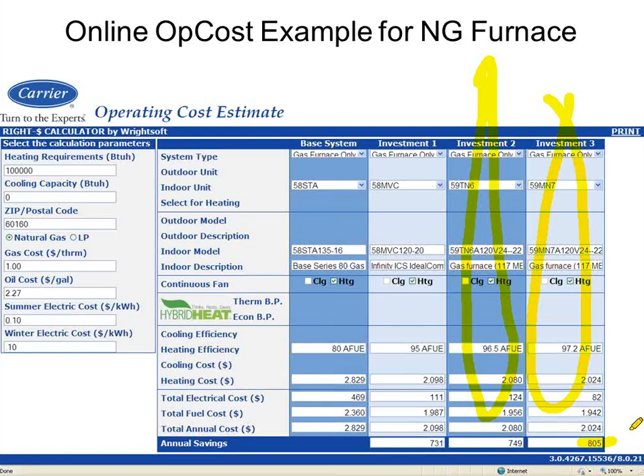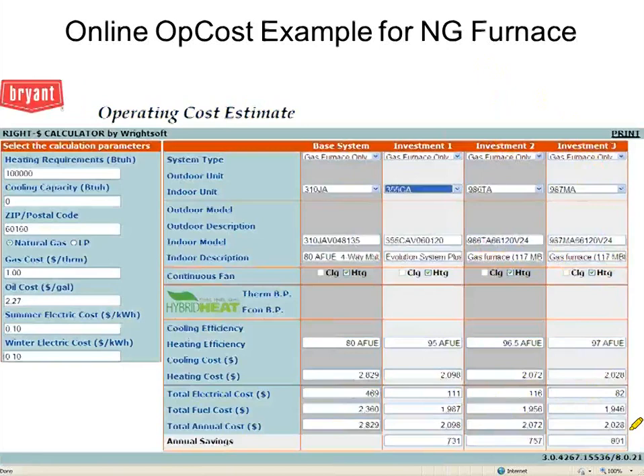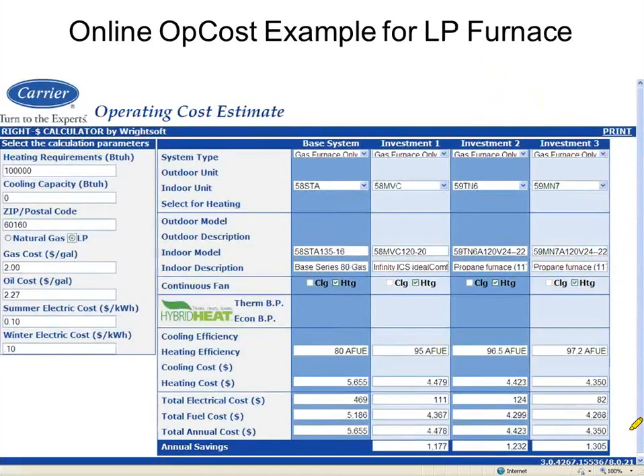And then we do the same thing with the inducer motor. We have it track the gas valve as well. So yes, it's going to keep a reasonably constant discharge temperature. It's not a fixed number, but we won't let it get below a certain minimum. If you look at propane examples, right? Excuse me, same exact furnaces with a propane example, same story, except because propane costs more, and actually it's probably more than $2 a gallon right now, but because propane costs more, the savings is more.